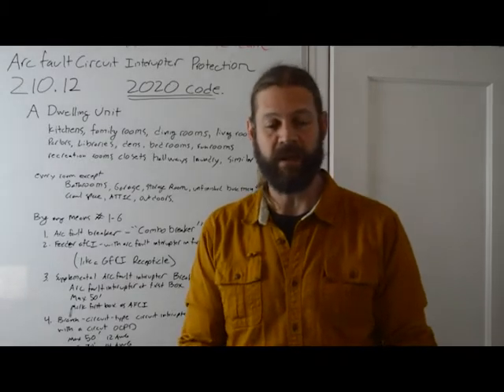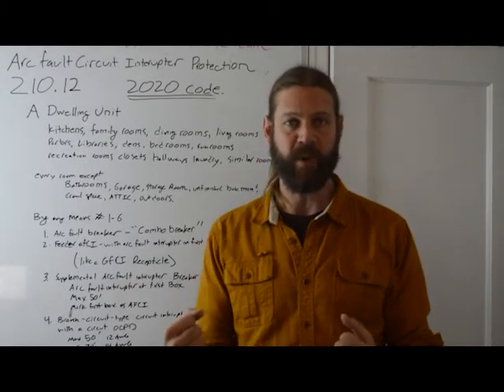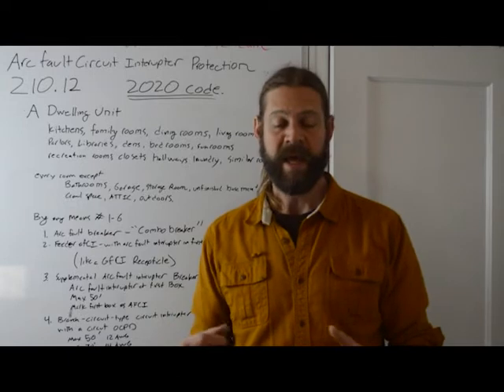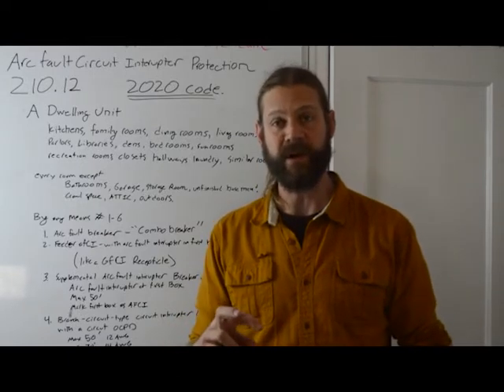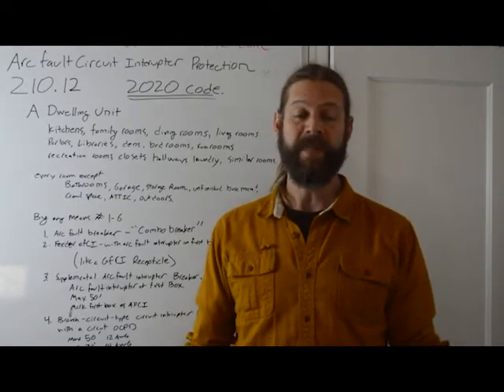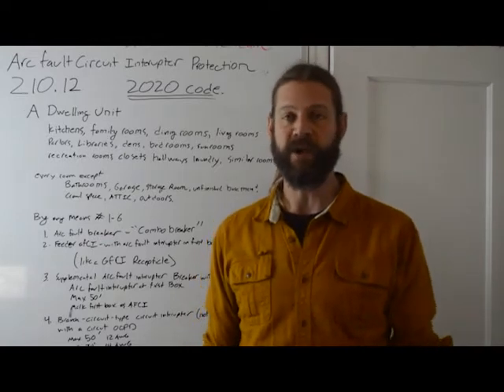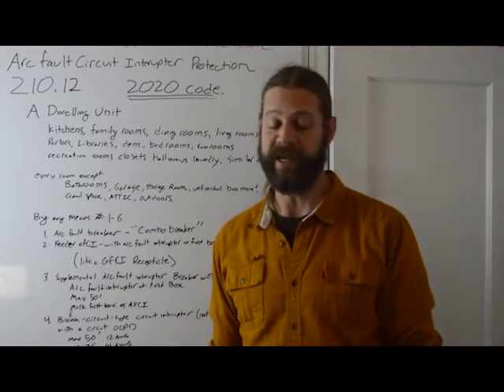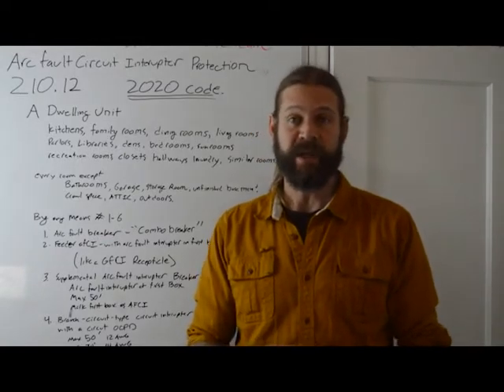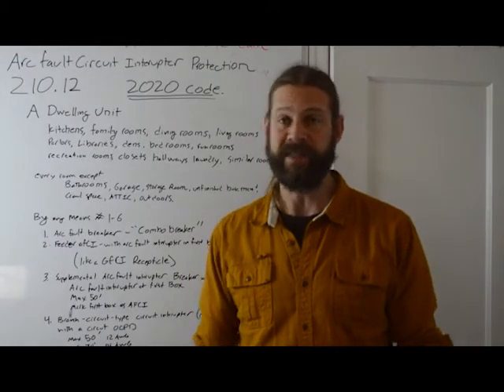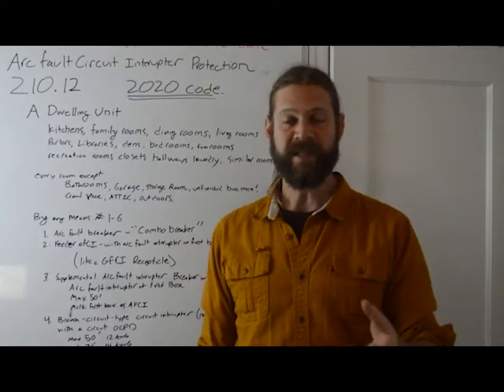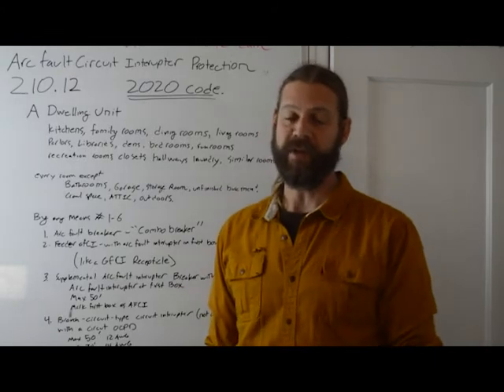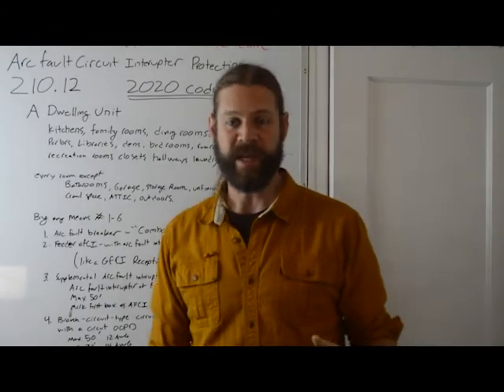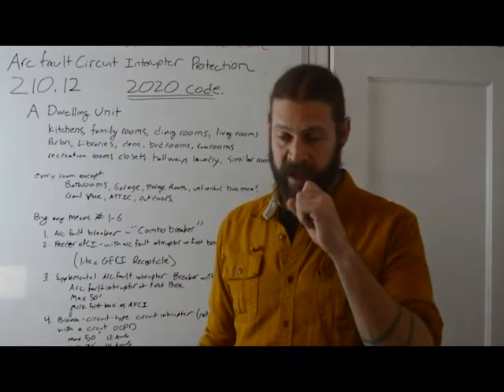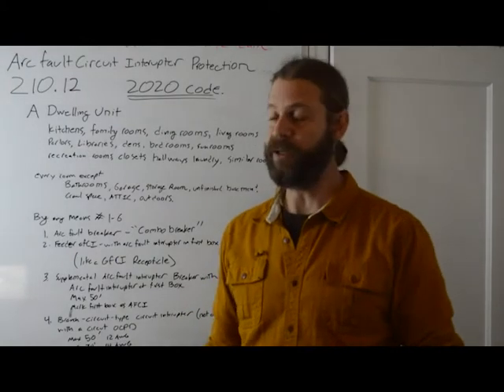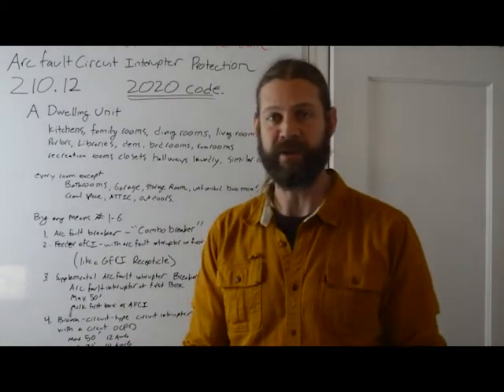So what happened a lot in old houses is the wire would actually pull away from the receptacle or the lamp holder, and it would create a little electric arc, and the electric arc wasn't a big enough resistance to cause the overcurrent protection device to engage. Like a welder, you can plug in a welder, use it all day, there's an electric arc, it doesn't trip your circuit breaker. So this electric arc won't trip a regular circuit breaker. So through the magic of computers and measuring the voltage and the current that goes through these, they can actually figure out if there's an electric arc in there.